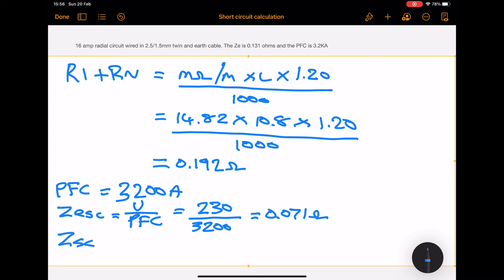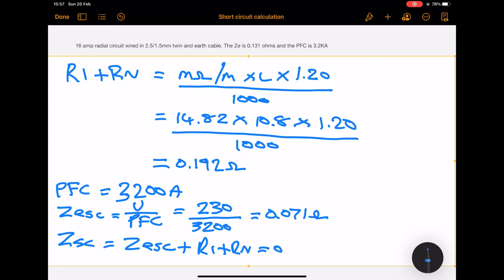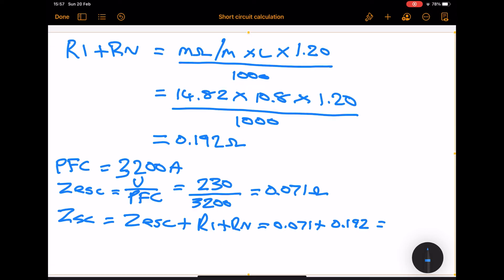We then need to find the ZSC, which is the impedance between line and neutral for the final circuit. We add the ZESC to the R1 plus Rn. So that's 0.071 plus 0.192 ohms, which gives us an answer of 0.263 ohms — the impedance between line and neutral for the final circuit.